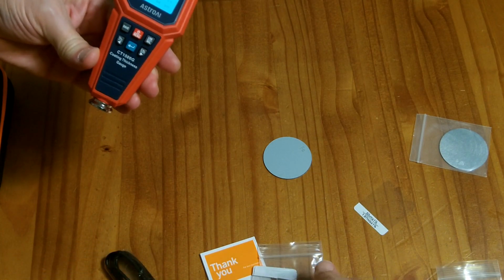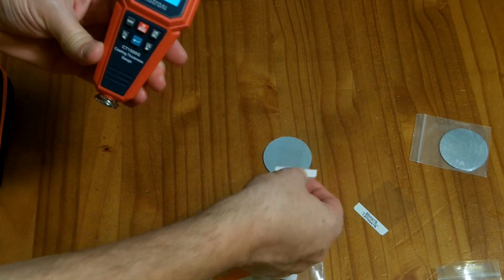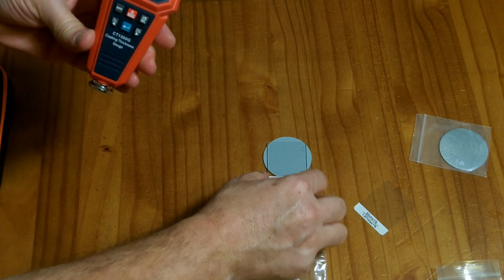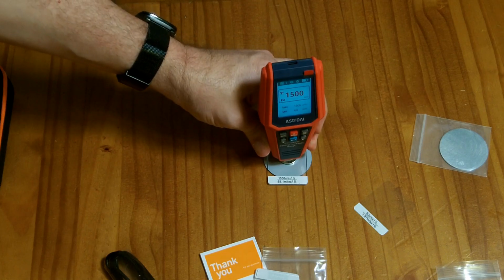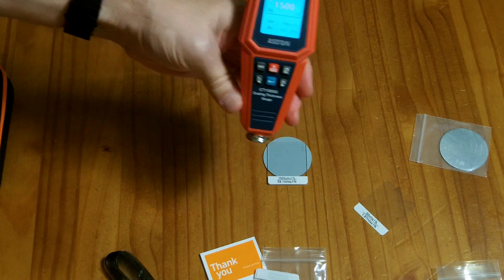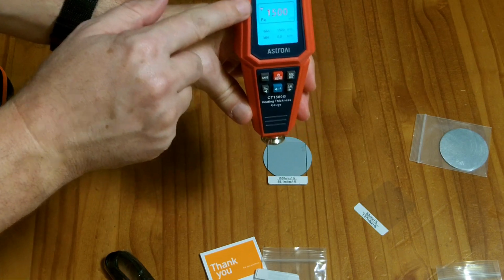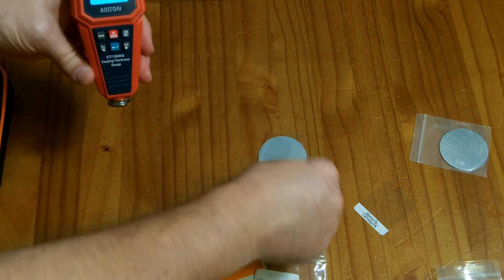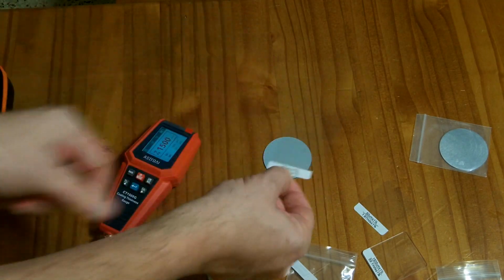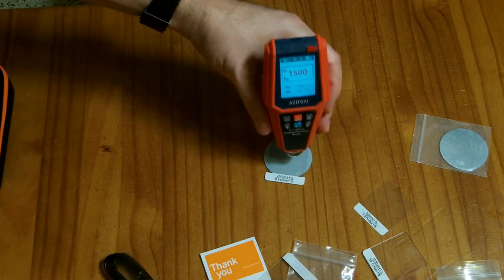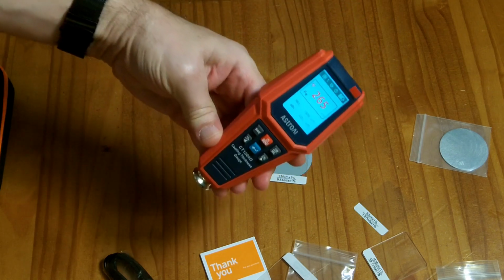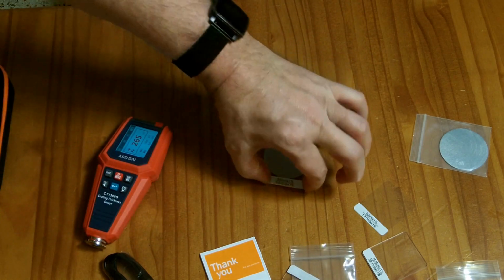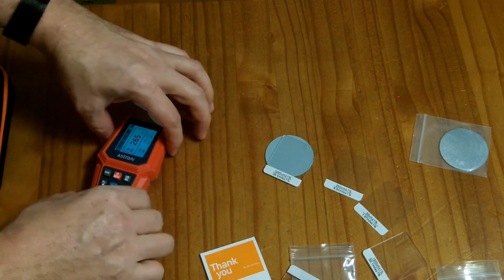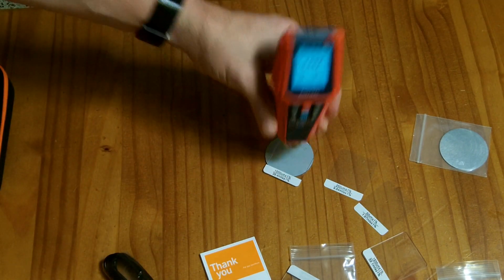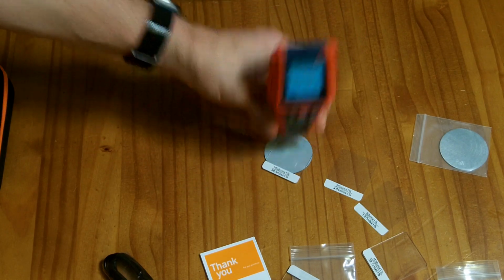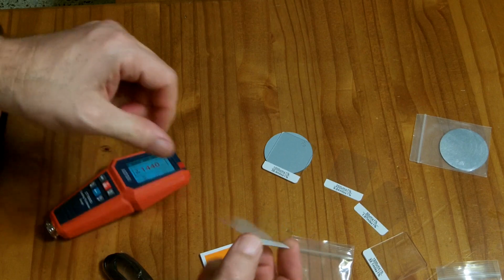Here's the thickest substrate, which is the 1,500 micrometers, or 59 mils. So that did come out at 1500, and it has the upper bound here, so it might say, well, it's either 1500 or above. So this here is 250 micrometers. So it says 265. There's the 1000. So we're at 1442. So it does look like it needs calibration here.